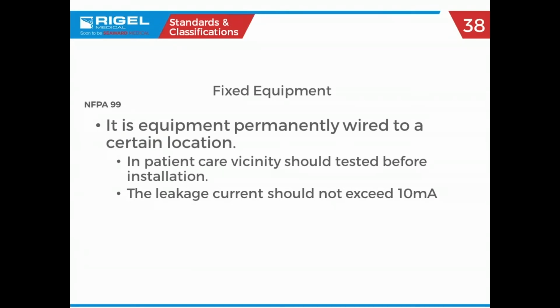So fixed equipment, physically hardwired into the electrical system of the facility. Maybe the good example of that is OR lights, right? You still have to test them because you reach up and grab that handle, which can often be metal, to reposition the light, so they still have to be electrical safety tested. But to do that, we do something called point-to-point, because we can't obviously plug it into our safety analyzer. We have to have the ability to do point-to-point testing, which basically is kind of like a multimeter, 2 probes, and we'll look at potential and such. So fixed equipment, leakage current should not exceed 10 milliamps. Period.